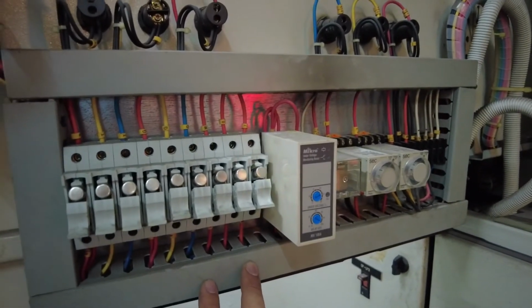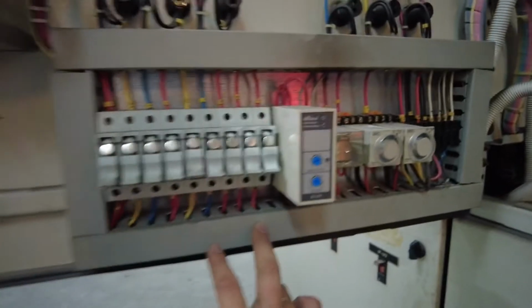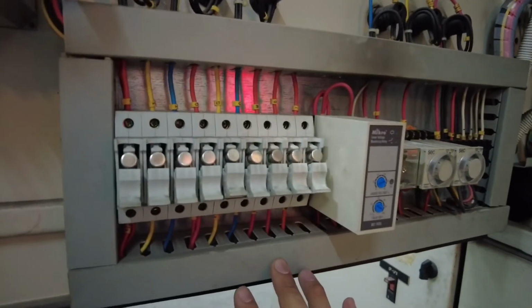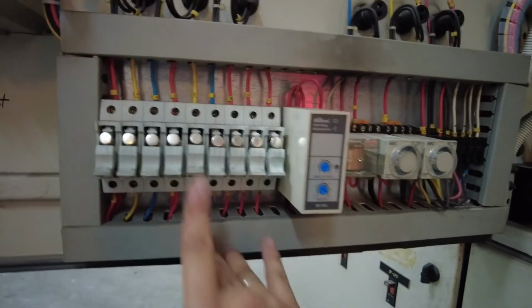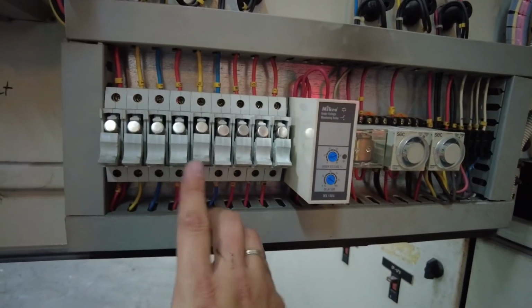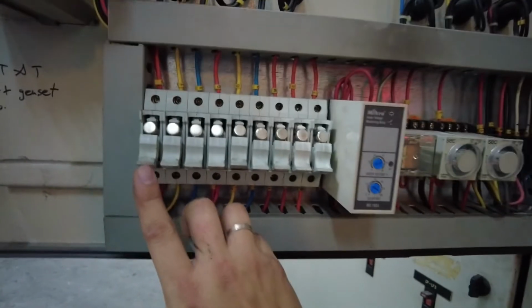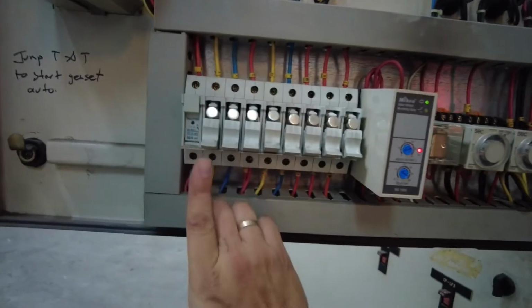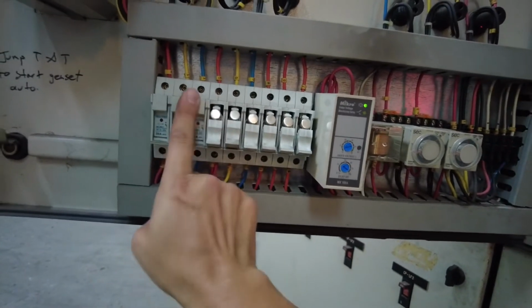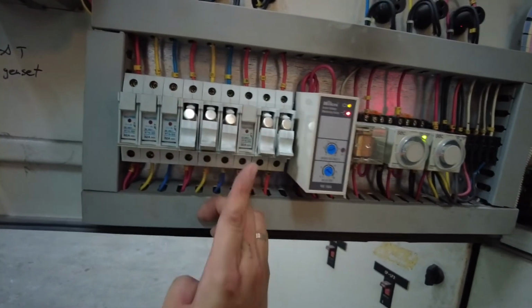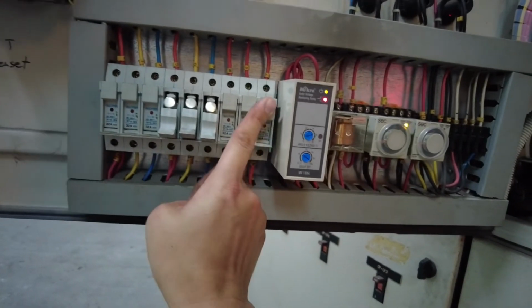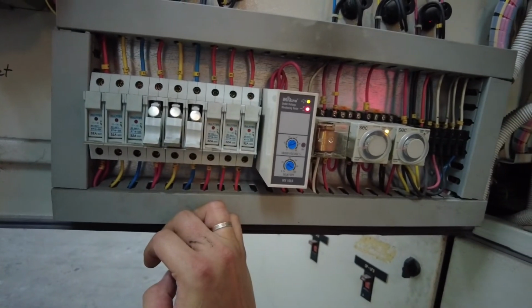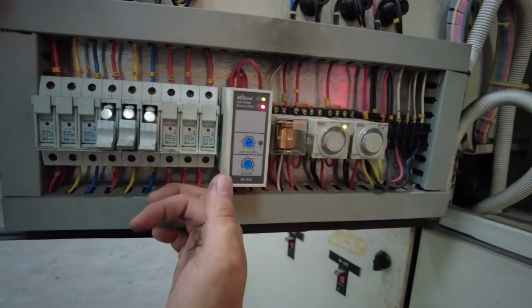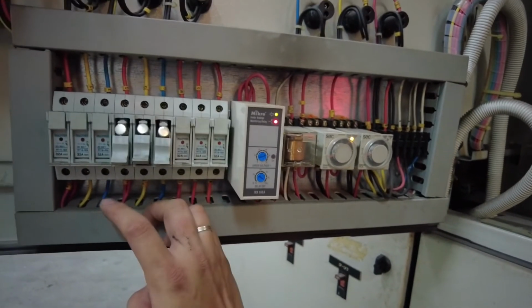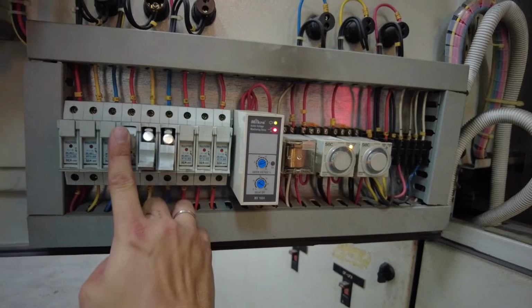I can hear the genset is running. Once the genset is running already, don't put back the genset fuse first. Put back the main supply fuse first. And here. Allow this to operate first and become steady. Now only you put back the genset fuse.